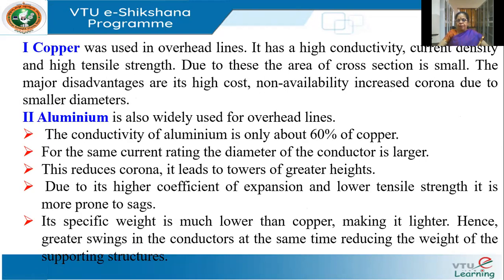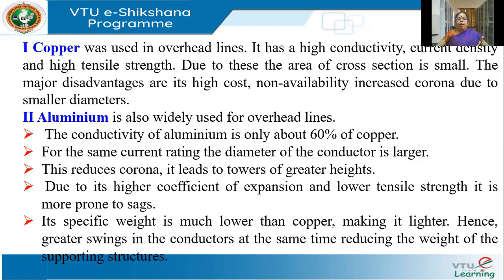The earliest choice was copper — very expensive, with very small cross-section area, so mechanical strength is not very good, and availability of copper is also not high. It immediately got replaced by aluminium. The conductivity of aluminium is only 60% of copper, so for the same current rating the conductor will be of larger diameter, which gives it better mechanical strength and also leads to reduction in corona. However, aluminium, because of its lighter weight, is more prone to sag and greater swing in wind.